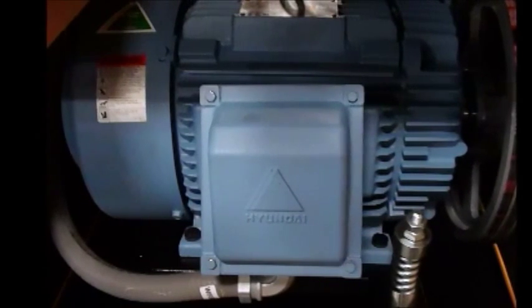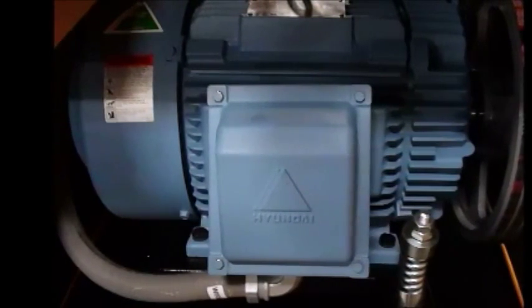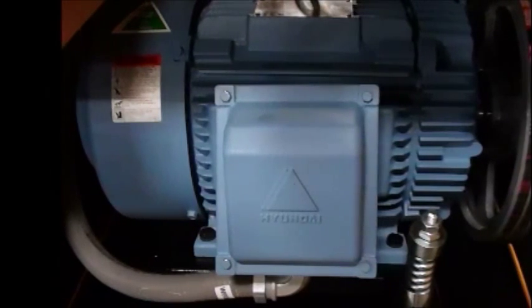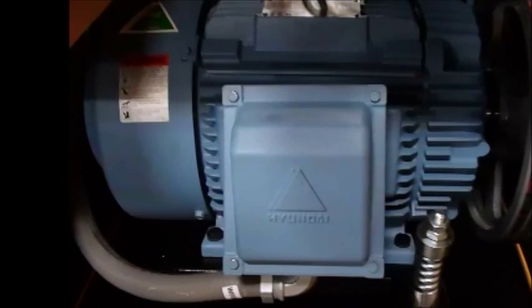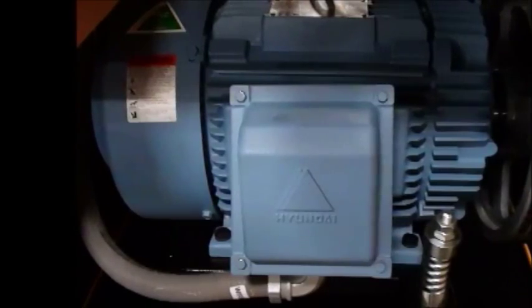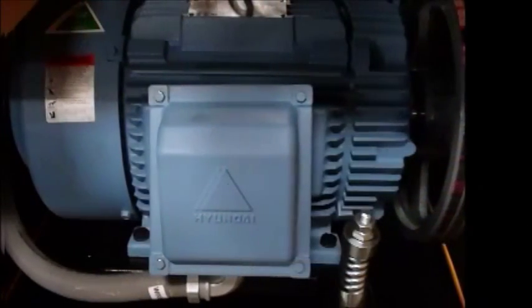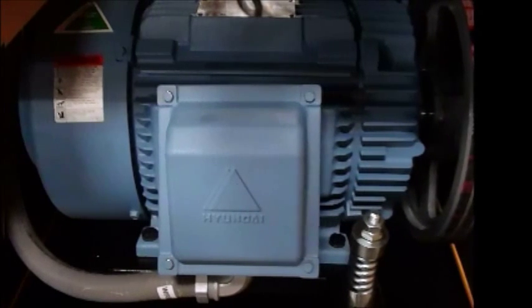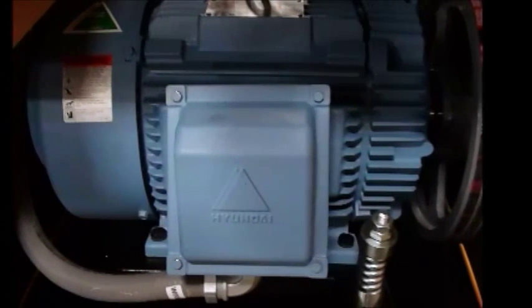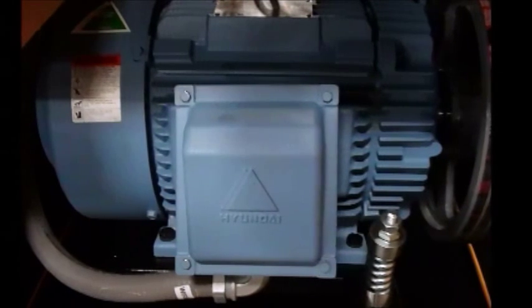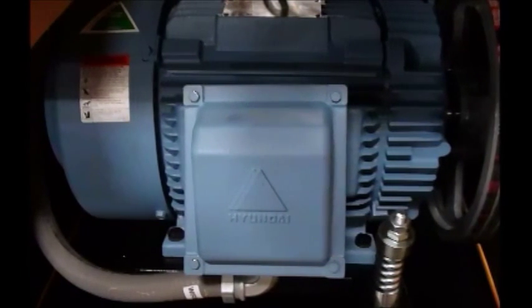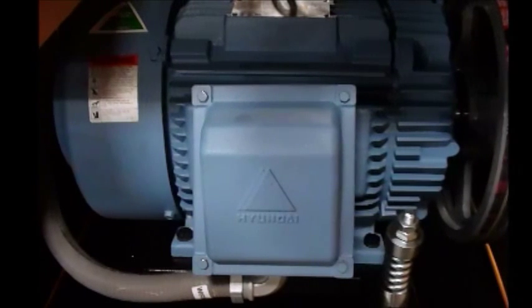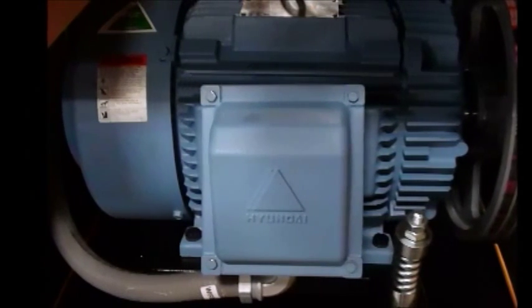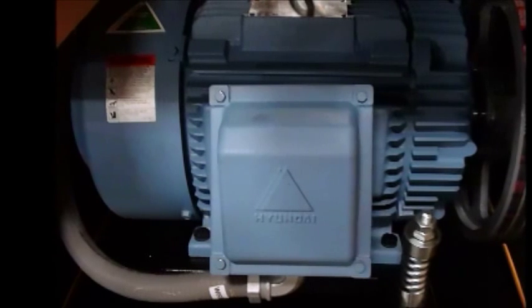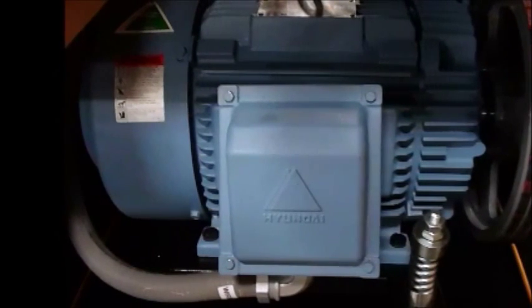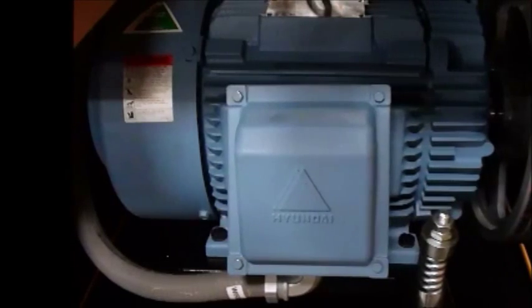MG-1, Table 12-12. NEMA design ensures that mating components, sizes, and bolt patterns are U.S. standard. To name a few: motor shaft length, shaft diameter, shaft key width, and mounting bolt hole patterns. It comes with a cast iron frame with conduit box with deep fin design for maximum cooling, and is also suitable for Y delta soft start through 12 lead design. Last but not least, the motor is inverter variable speed ready.